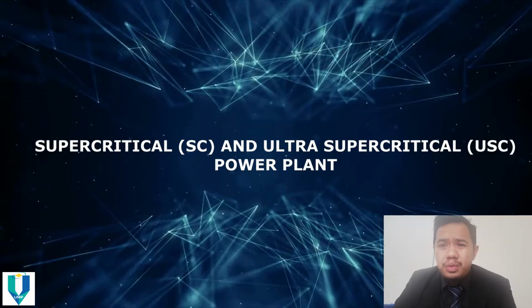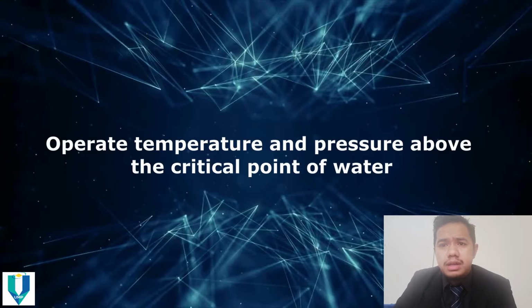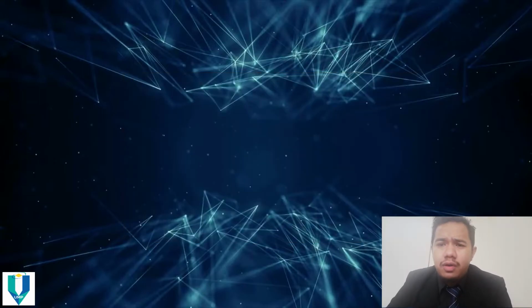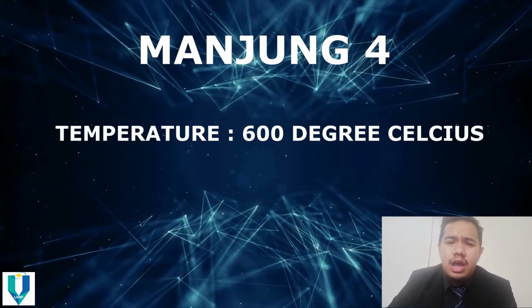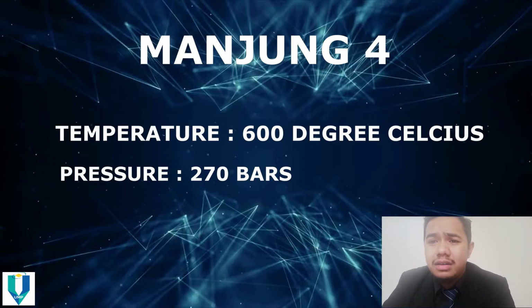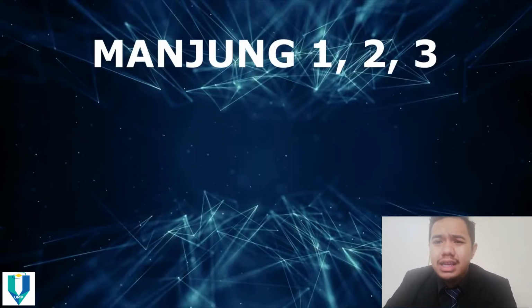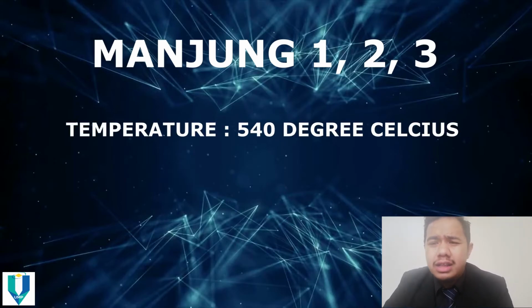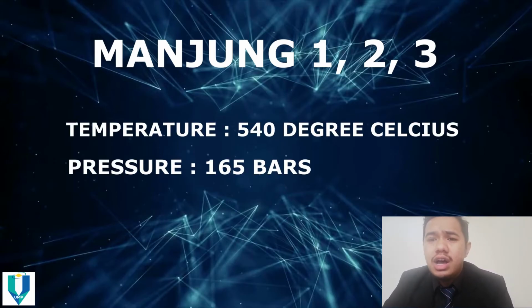At TNB, supercritical and ultra supercritical power plants operate at temperature and pressure above the critical point of water. That is the temperature and pressure at which the liquid and gas of water coexist in equilibrium. The combustion temperature at Manjung 4 is around 600 degrees Celsius with pressure reaching 270 bars, while at Manjung 1, 2 and 3, the combustion temperature reached 543 degrees Celsius with pressure of 165 bars. This helped to reduce the use of coal at Manjung 4 compared with Manjung 1, 2 and 3.